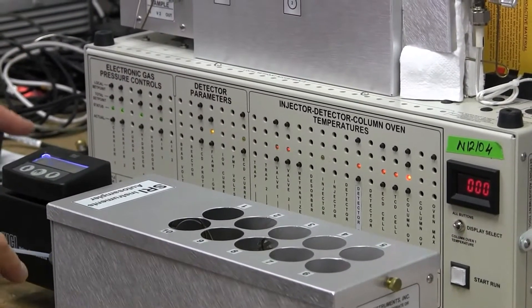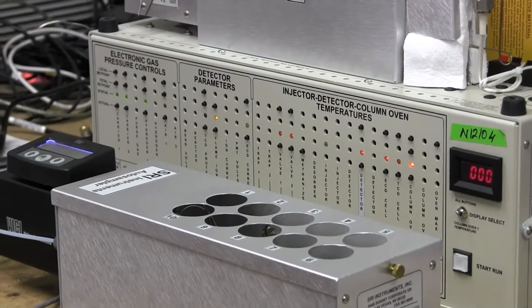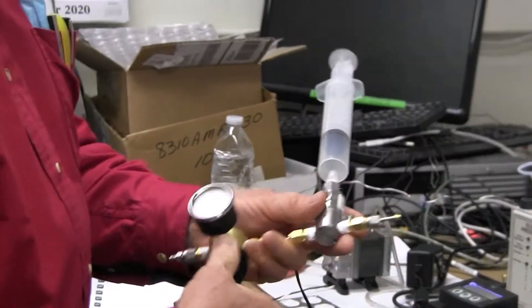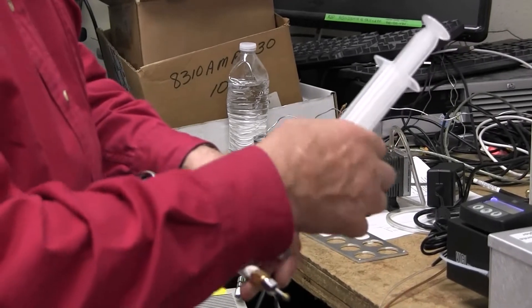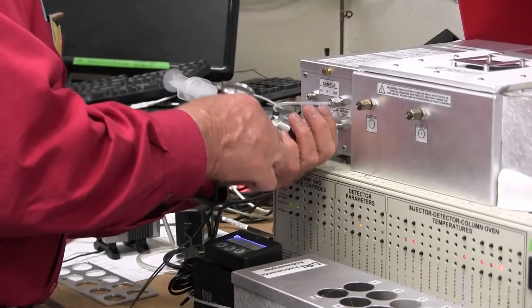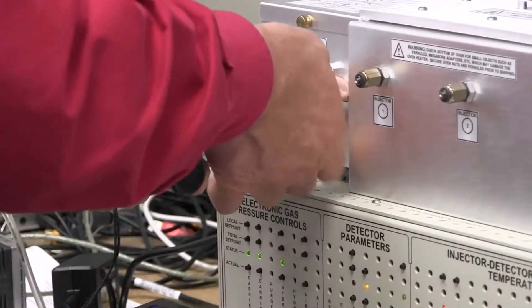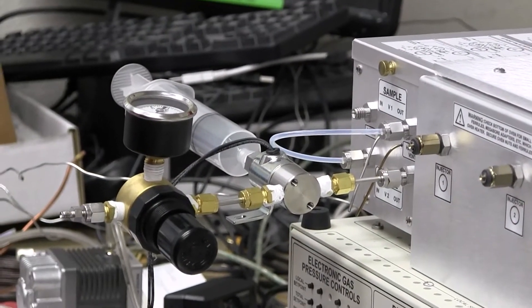You can just push the up button and the little valve inside moves. There's also this part of the kit, which is a solenoid valve, a pressure regulator, and then a 60-milliliter syringe with a Luerlock connection. So this has to be connected to the sample outlet port. Nice and tight, should just sit there by itself.